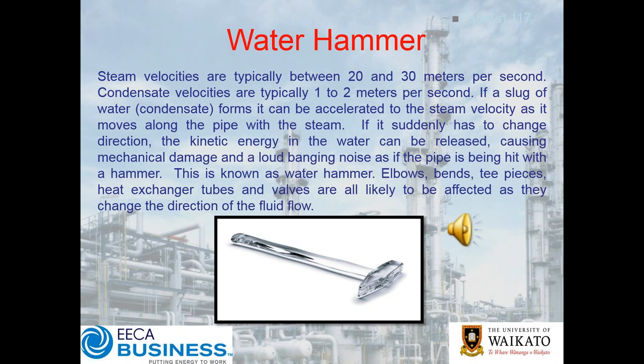Where you have both condensate and steam in a pipe, you can form a slug of water or condensate. If you've got steam pressure behind that condensate, that can accelerate that plug of liquid to the speed of the steam velocity. When that slug of condensate comes to a sudden change in direction, the kinetic energy in that water gets released, causing mechanical damage and the banging noise that you typically hear.